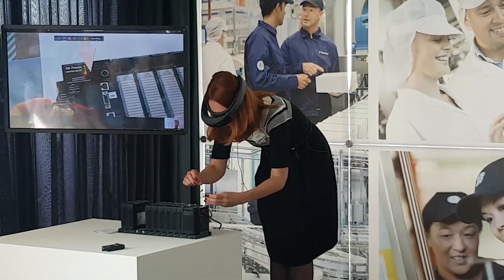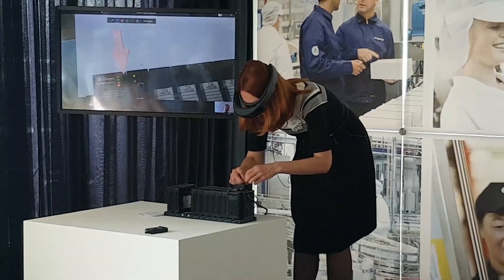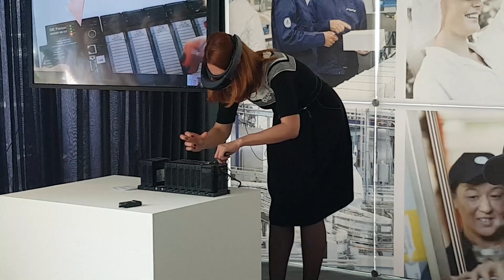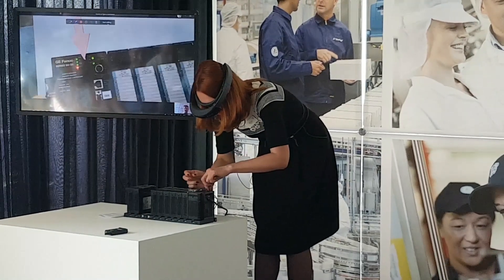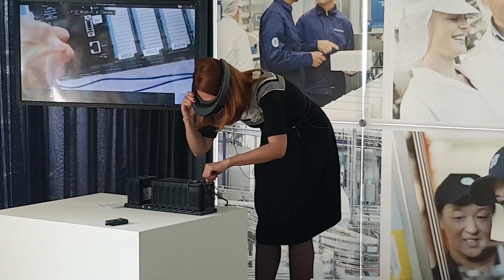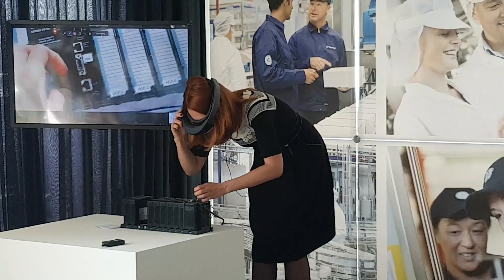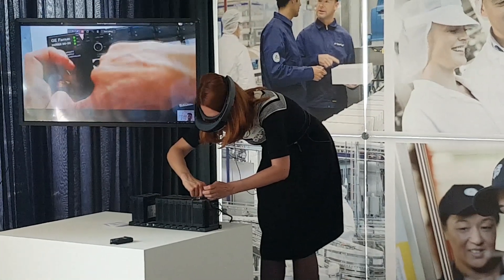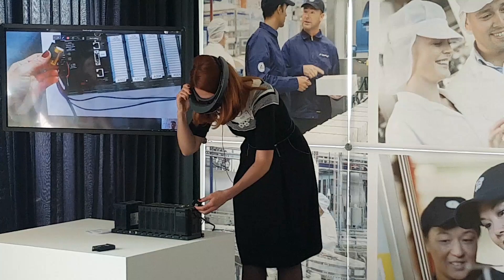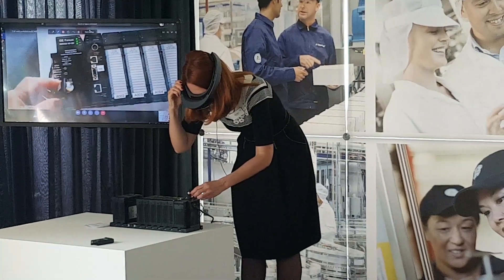Okay, then it's clear. Can you show me? There are some contacts — be careful, they're a little bit tricky. You have to connect them and let's see if the battery is full — it's okay. Then the alarm should disappear. Can you show it to me? A little bit more down, correct. Just to get the direction, correct. Can you show it to me — just check together. Looks okay. I think the alarm has disappeared. Perfect, very simple, very easy.